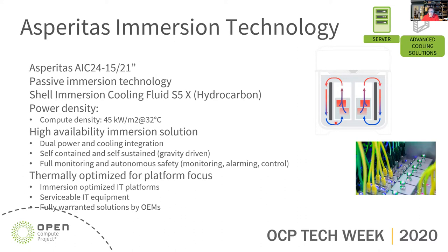That heat is generated by IT equipment, which brings me to the relevance of IT design in this setting. We exclusively work with optimized IT equipment where all the hottest components are positioned at the bottom of a tank. These components heat up the liquid — the liquid absorbs that heat, expands, warms up, and rises to the surface. In the same liquid bath, water-cooled heat exchangers are immersed, transferring thermal energy from the dielectric fluid directly into the facility water circuit.